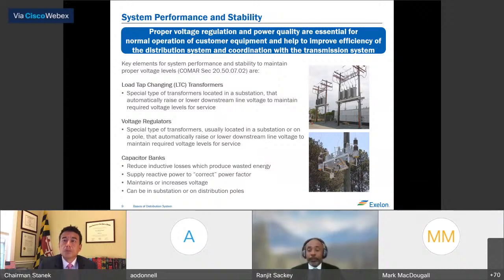So not only is it important to maintain capacity for our customers, but it's also essential to manage the voltage change between the substation and the customer service point at all times. For example, in Maryland, we have COMAR rules that say voltage at the utility service terminal should be within 5% for 120 volt service. So the utility has to make sure that the service voltage is maintained within that range. Providing customers with proper voltage and power quality is essential for them to be able to use their equipment appropriately. It's also essential to operate the grid efficiently, minimizing power losses.